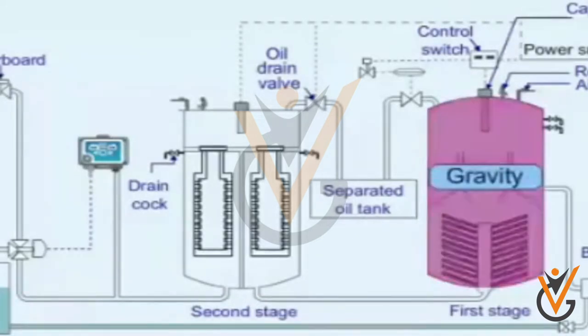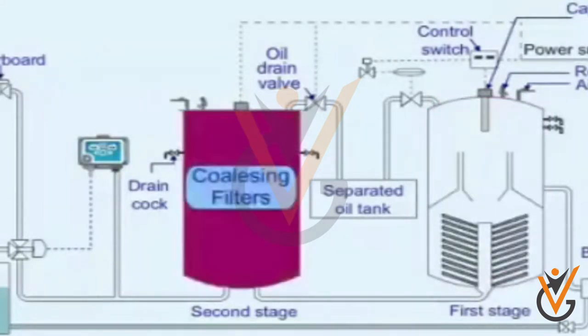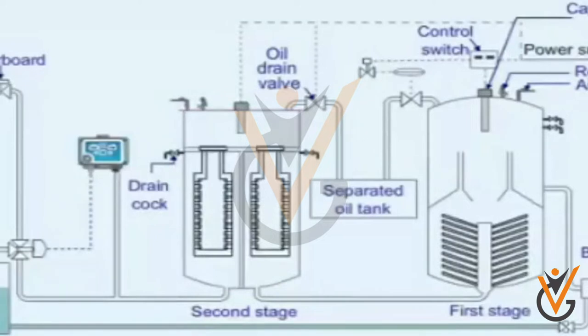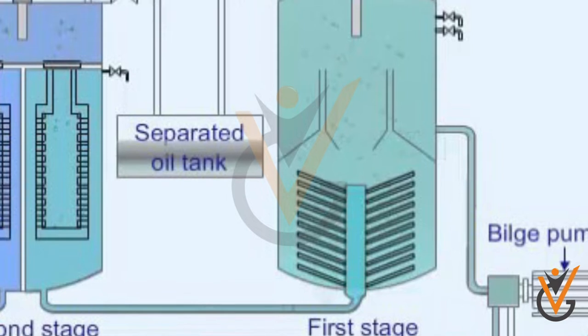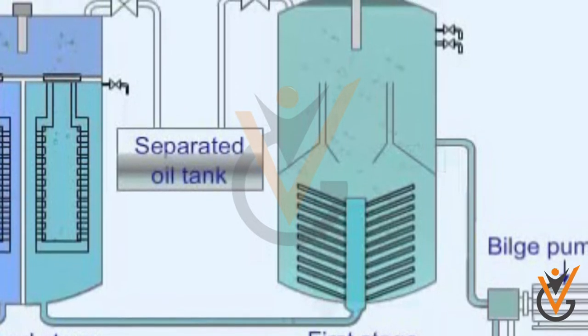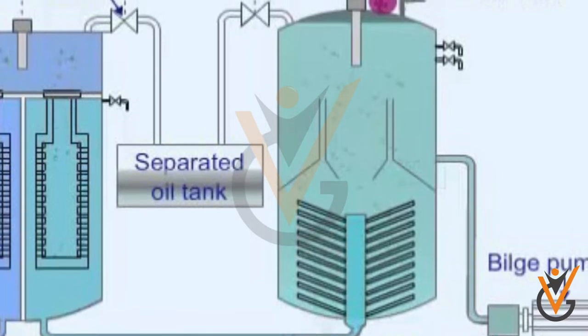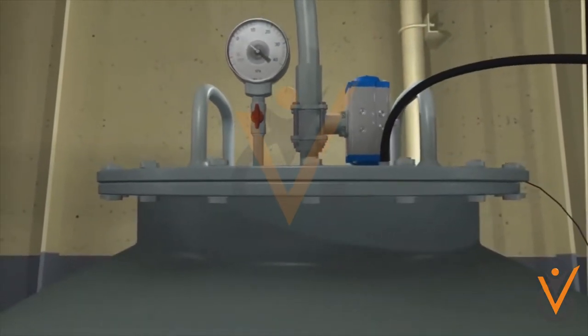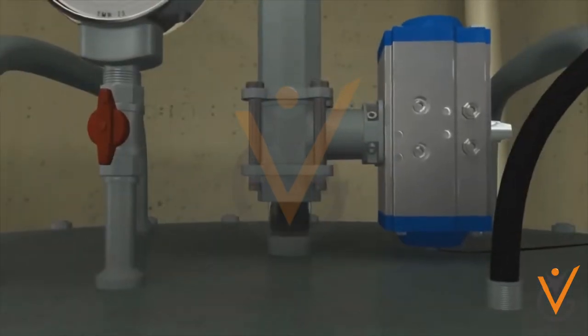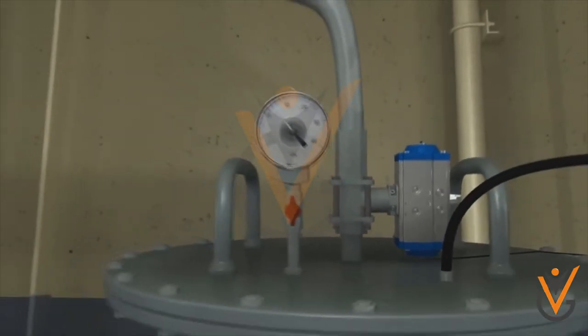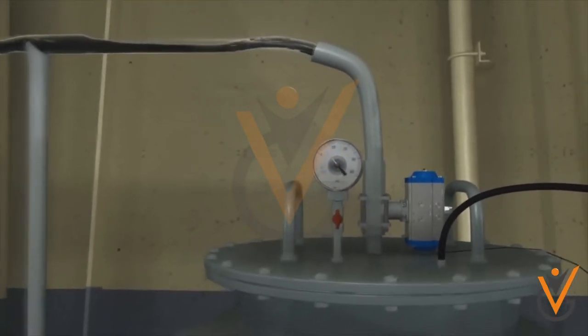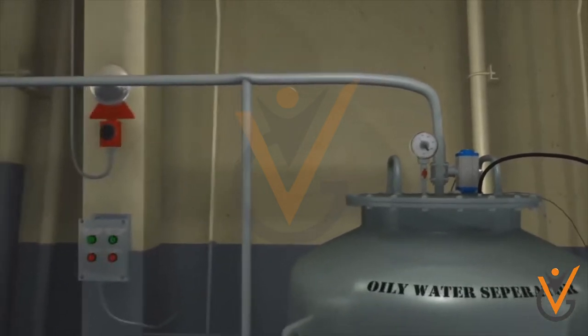Oily water is pumped to the first stage — the coarse separating compartment. Here, oil with a lower density than water rises to the surface, aided by heating coils, in what is known as the collection space. This unit consists of catch plates inside the coarse separating compartment and an oil collecting chamber. Over time, more oil separates and collects in the oil collecting chamber, where the oil content of the water passing through is around 100 parts per million. A controlled valve — pneumatic or electronic — releases the separated oil into the designated sludge tank. A heater may be incorporated for smooth flow and separation.